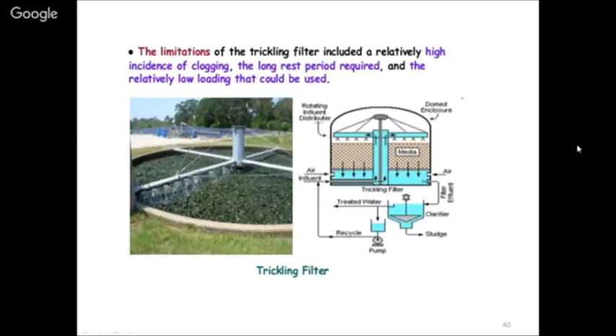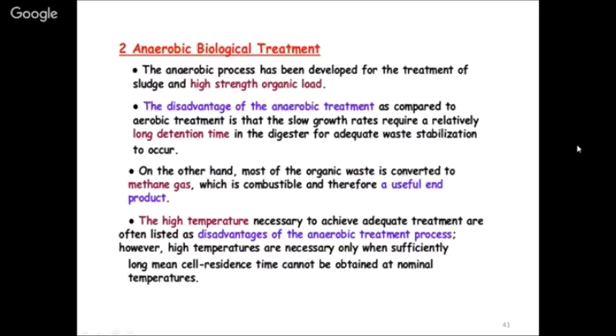Anaerobic biological treatment operates in the absence of oxygen and is used for sludge and high-strength organic wastewater. Very high BOD values - around 10,000 to 30,000 mg/L - call for anaerobic treatment, sometimes even with small flows but high BOD. The key design parameter is total load: flow multiplied by concentration. If organic content is very high and discharge is comparatively small, or if organic load is very high even with larger flows, anaerobic biological treatment is used. The biogas plant is a typical example of an anaerobic biological treatment plant.